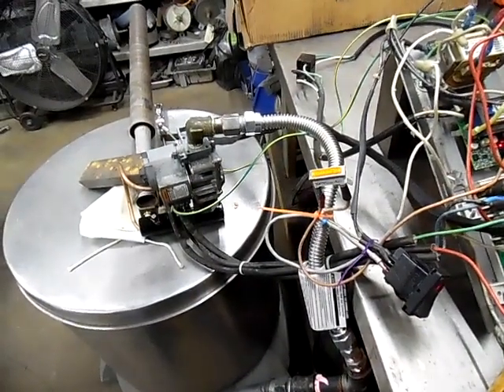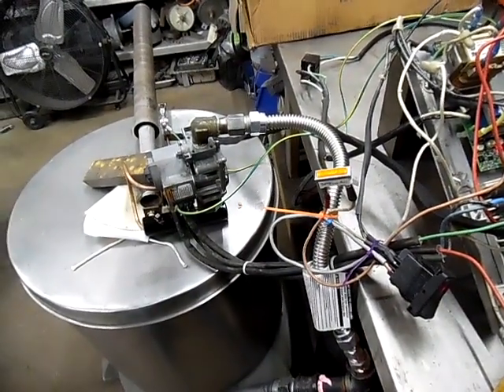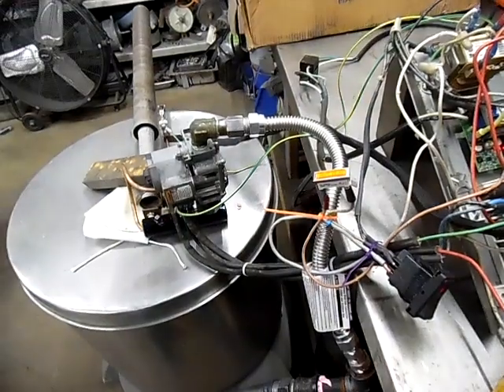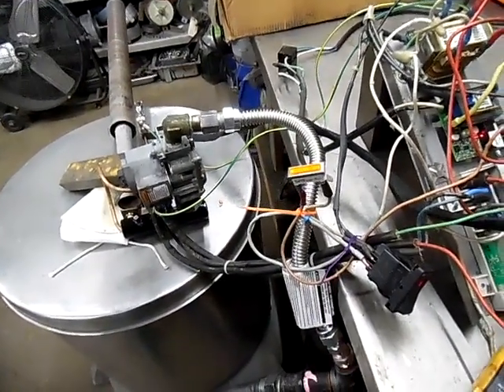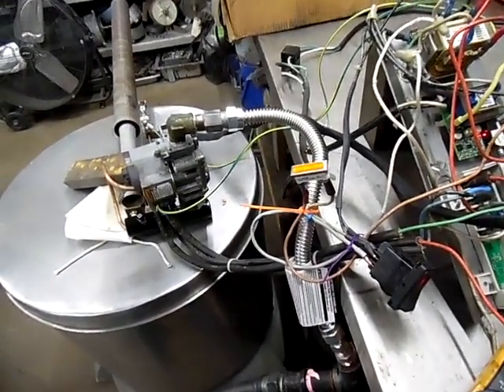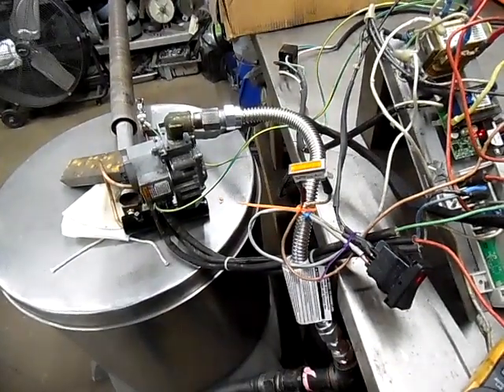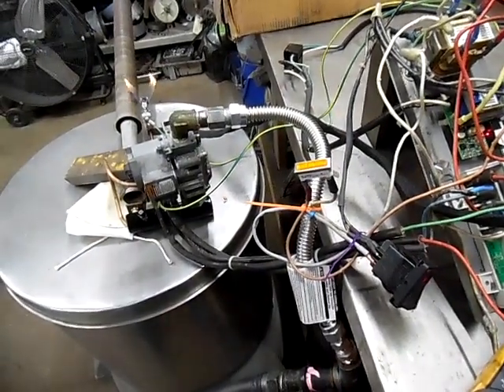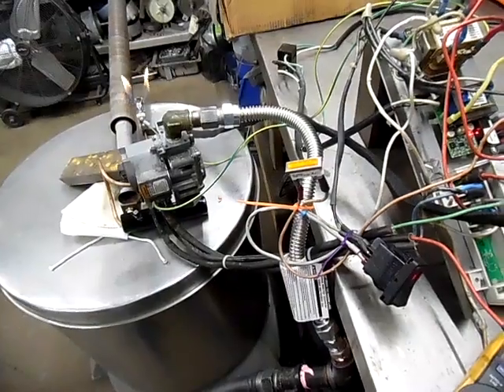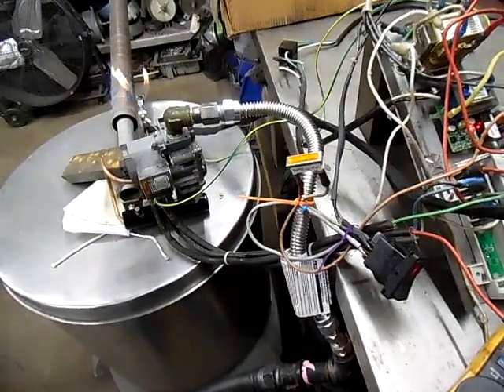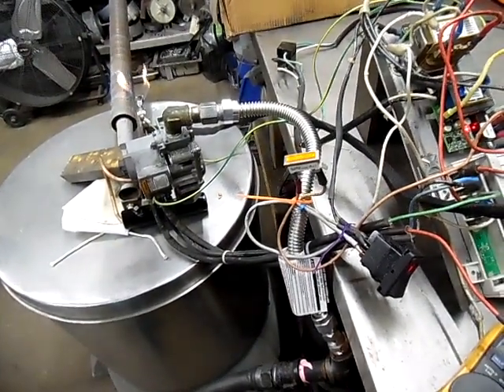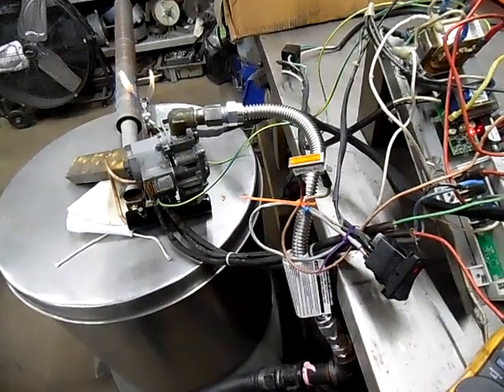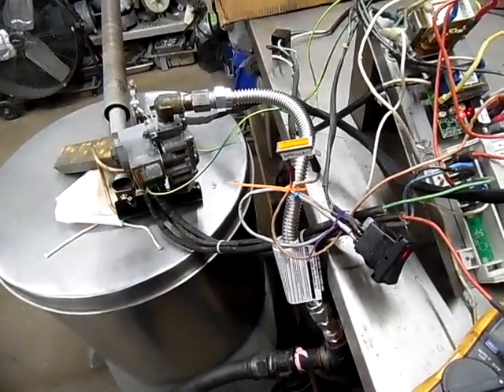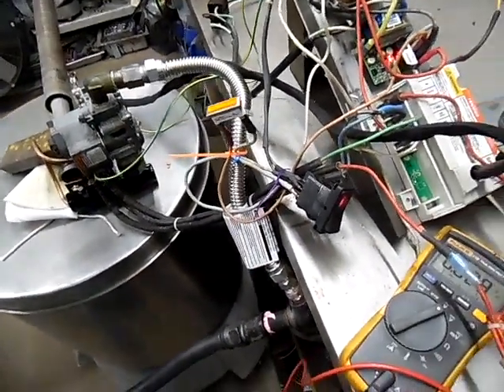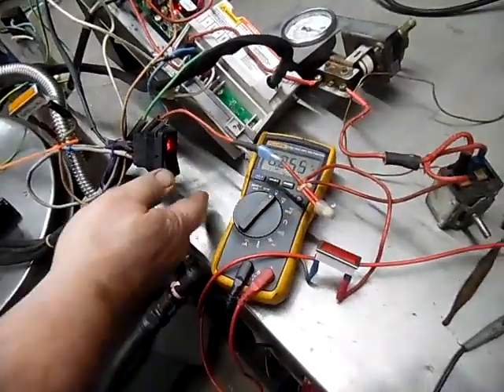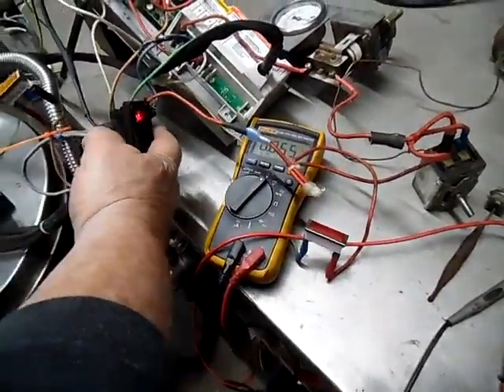If you turn the temperature down, the pilot will stay lit, but the main burner will shut off. And because it only goes through the MV circuit, when you turn the temperature up on your thermostat, your pilot will come on, and then it'll turn the MV on, and again it lights the burner back up. So this is the basic operation of this particular kettle, and you will find most kettles work the same way.